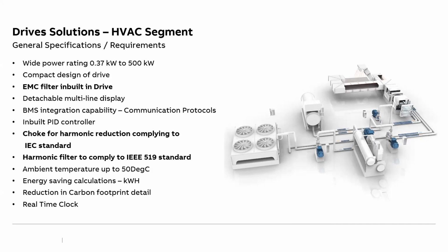Then some other additional features like kWh calculation, what is the kWh consumed, the energy savings achieved over a period of time, and then the real-time clock. This is one important feature. The real-time clock basically performs two functions. One is the scheduling function, wherein you can schedule your entire day or your entire week, entire month, or even your entire year along with the holidays. It is a program, so you need not go and start or reduce the speed or shut down. It will automatically start in the morning, shut down in the evening. Plus, it will reduce the speed as per the time of the day.